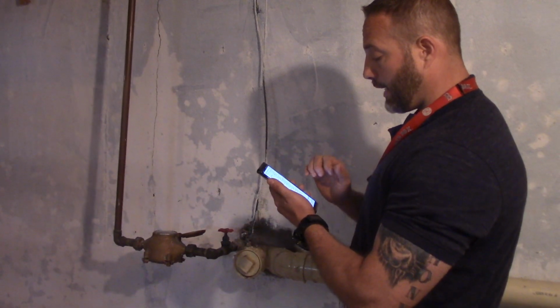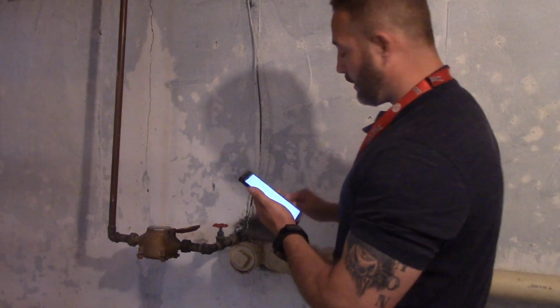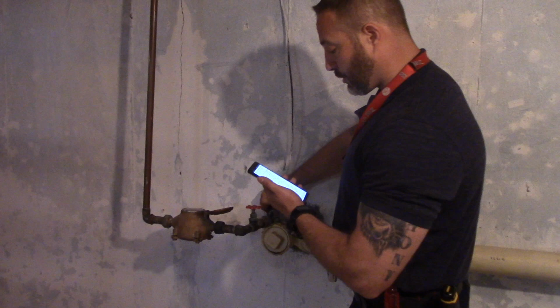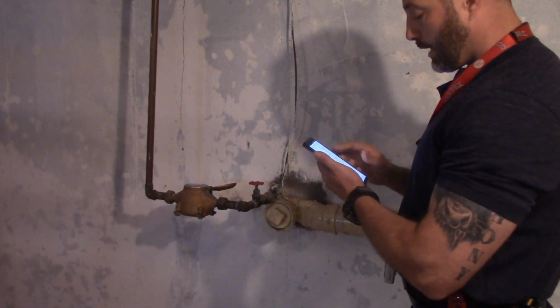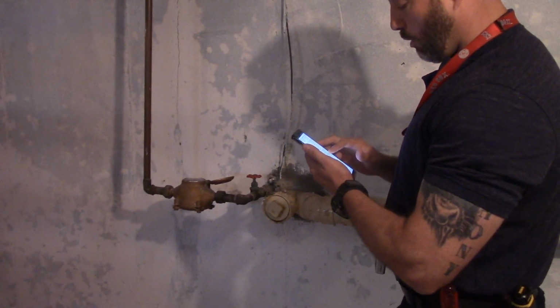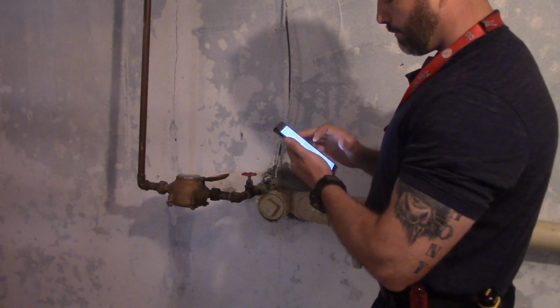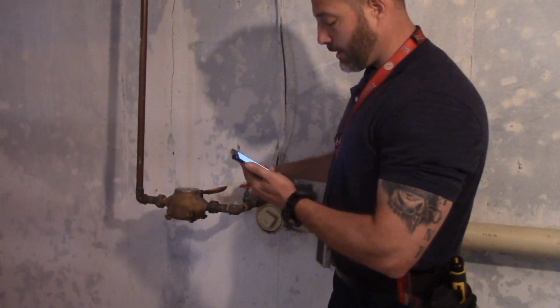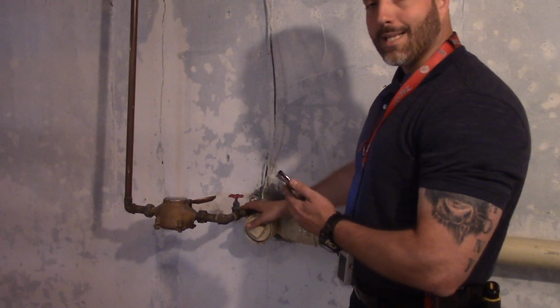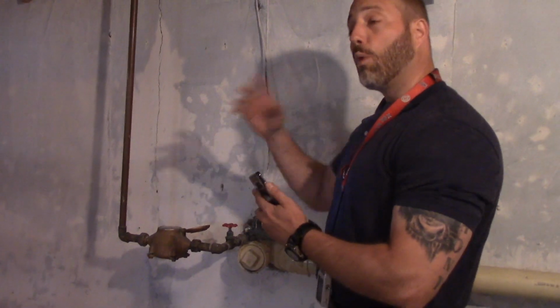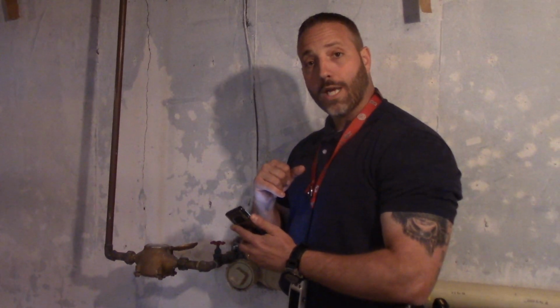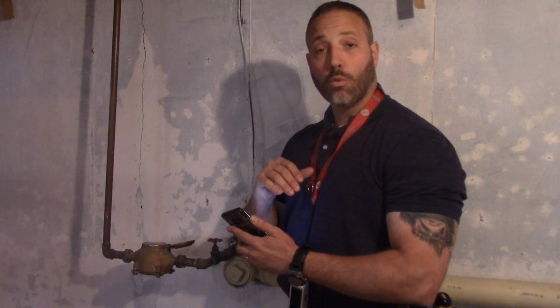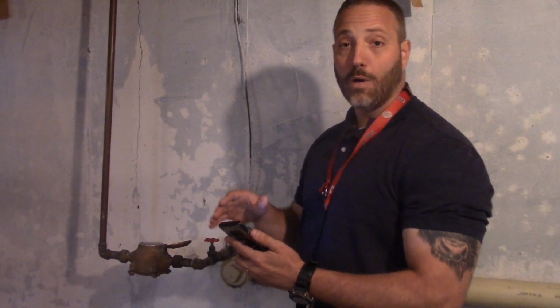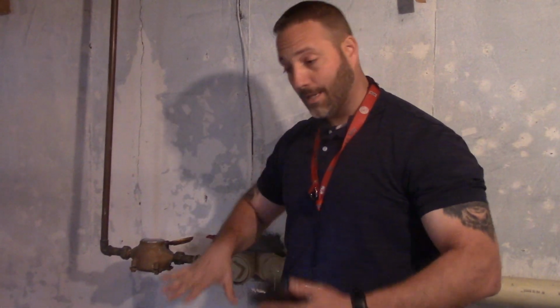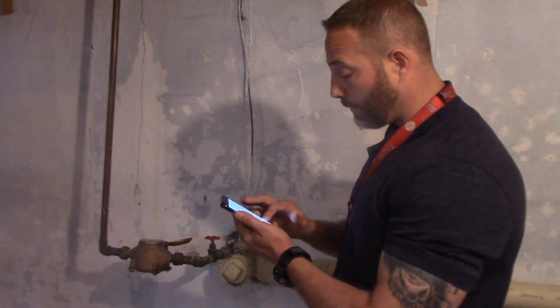Now the next item is we want to make sure that the connections are secure, which we have. We have a main water, if the ground is to the main water, and we talked about the missing jumper, but we also want to see if there's a ground rod. When we were doing the exterior wall section, I didn't see a ground rod. That doesn't mean it doesn't exist. It could be buried, but it's not visible. So I would definitely point that out.